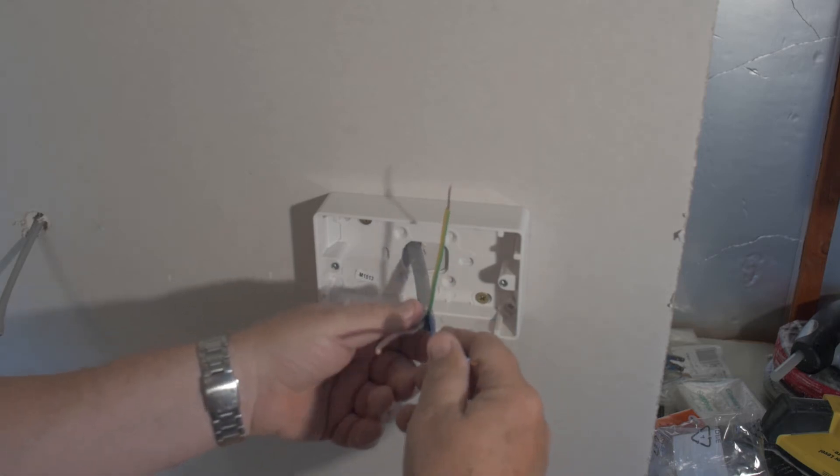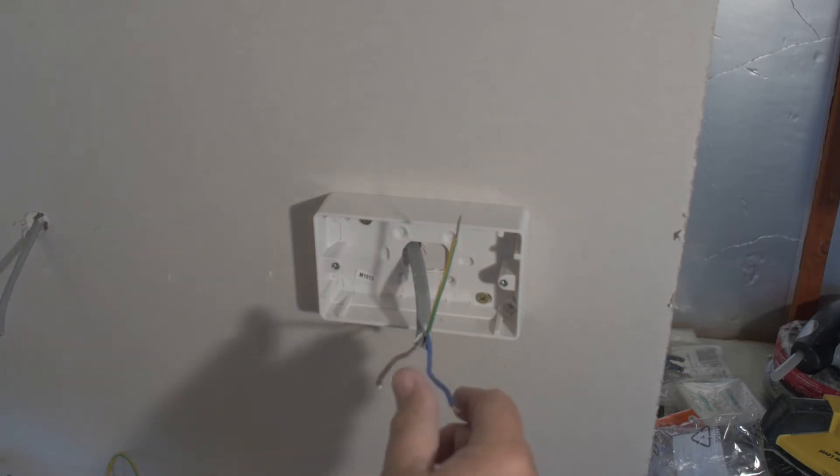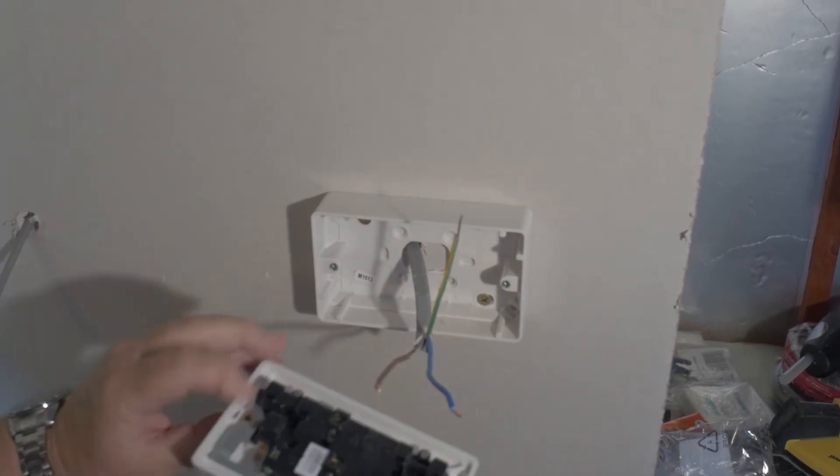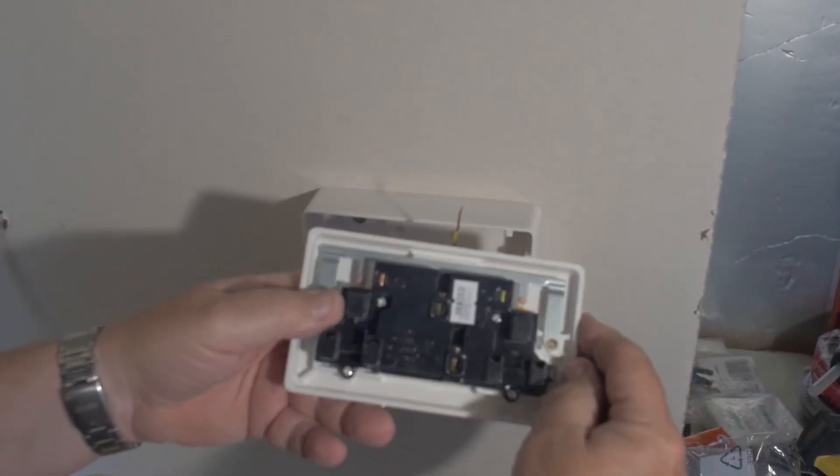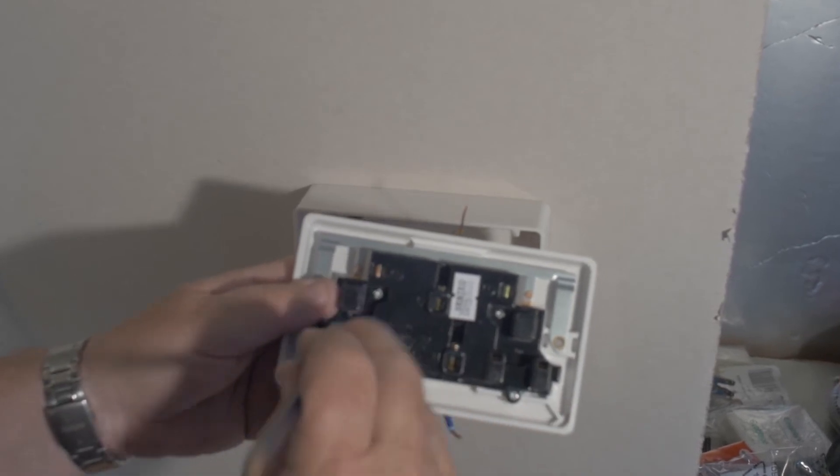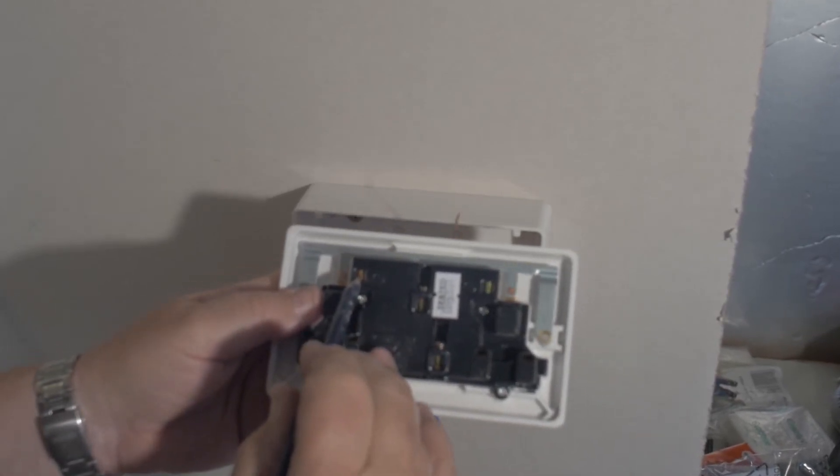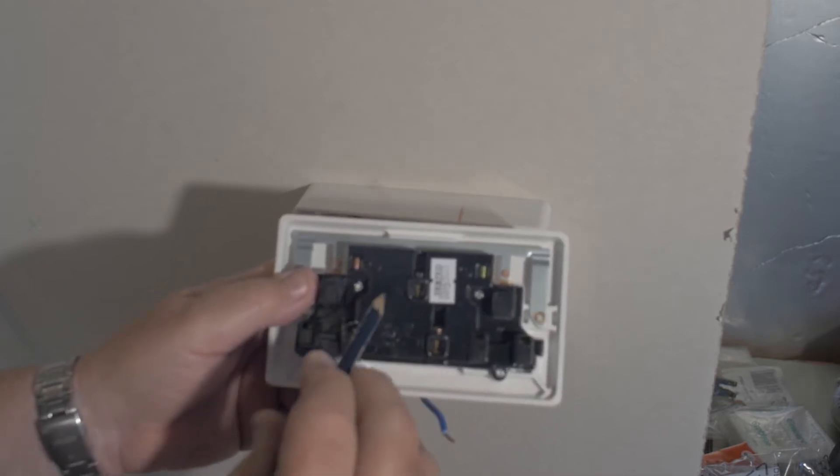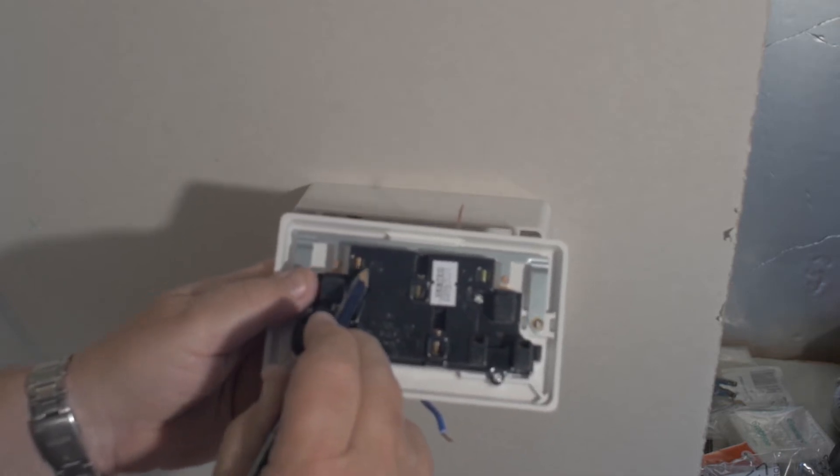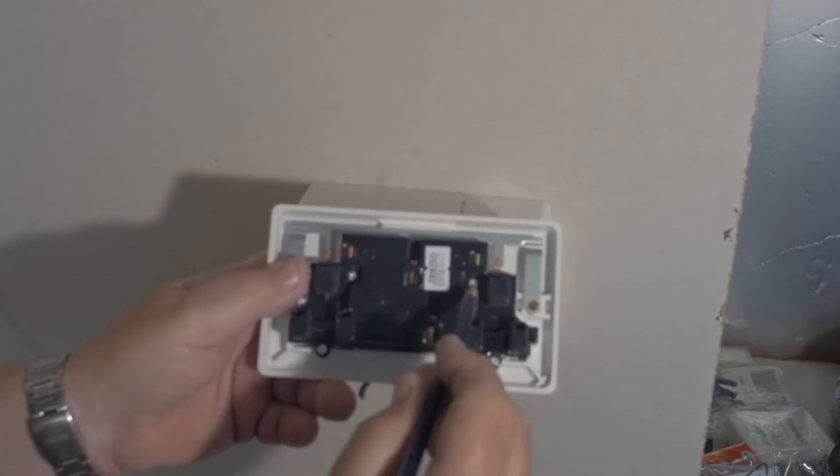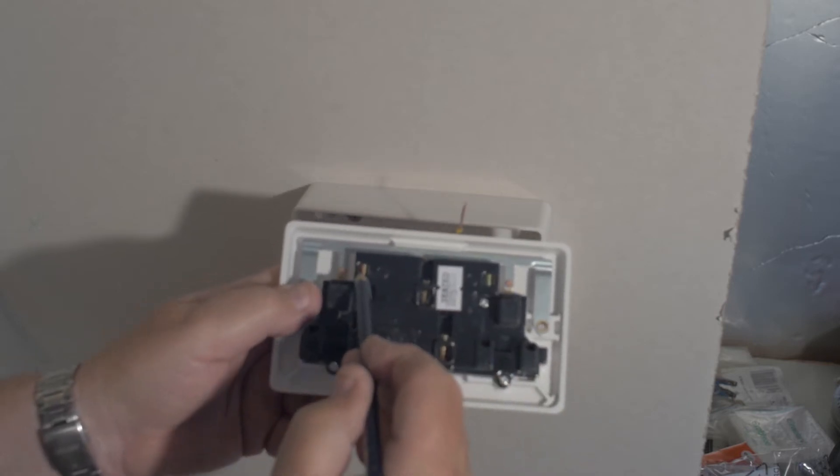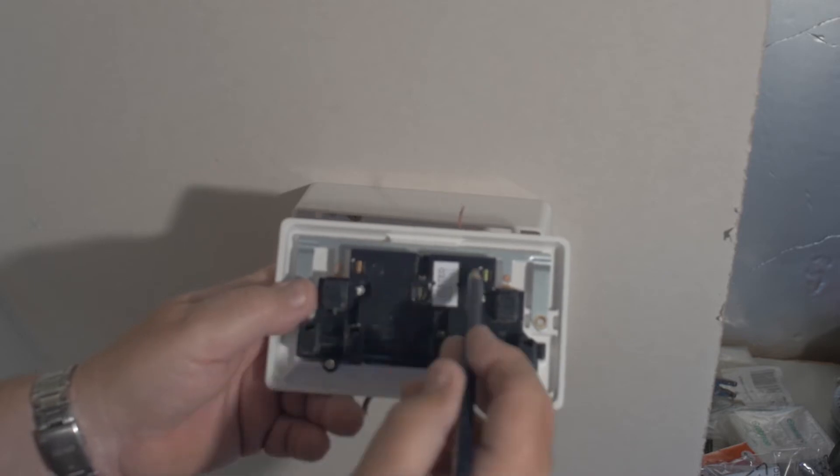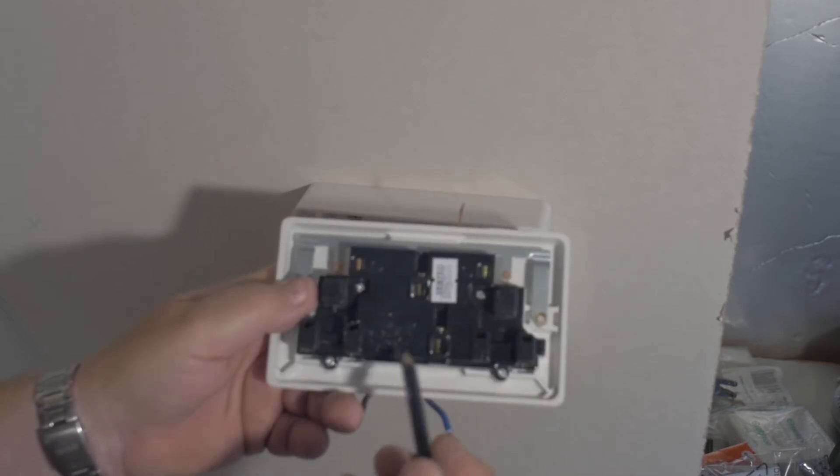Now it comes to installing the actual socket itself. So this is a socket we're going to use. If you look at the back of the socket, there will be an earth connection, a neutral connection, and a live connection. They're all clearly marked. The L is here for live and N for neutral. They're all clearly marked. You've got an earth cable here and an earth cable here. You only need to connect to one, but you can choose which one you connect to, but you only have to connect one.